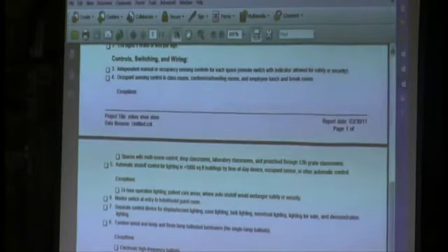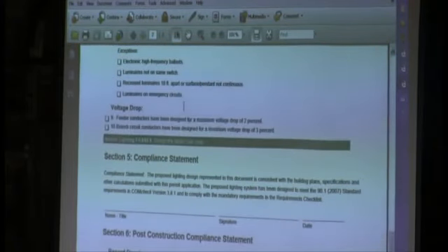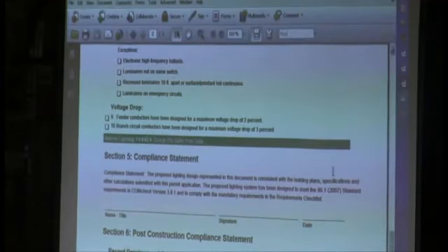So basically, probably the big thing would be the permit applicant, you're looking for this green line right here. Code Official, you're looking for this green bar that says your lighting passes by 6%. You sign it and submit it. So COMcheck does all your documentation for you, very quickly does all the math for you.